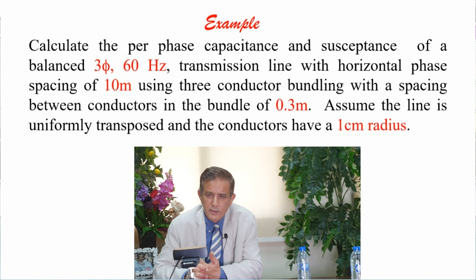Let's take one example. The example is to calculate the per phase capacitance with horizontal phase spacing of 10 meters, using 3 conductor bundling with a spacing between conductors in the bundle of 0.3. This is the same example we solved for the inductance. If you remember, we solved this one for the inductance. Now we'll do it for the capacitance. The equation is simple. The only thing is I want to find the equivalent distance between the phases and the equivalent radius for the conductor in the bundle.